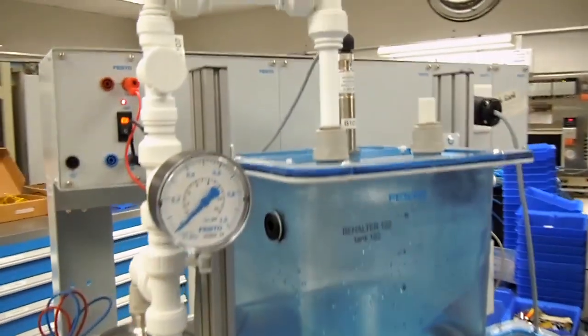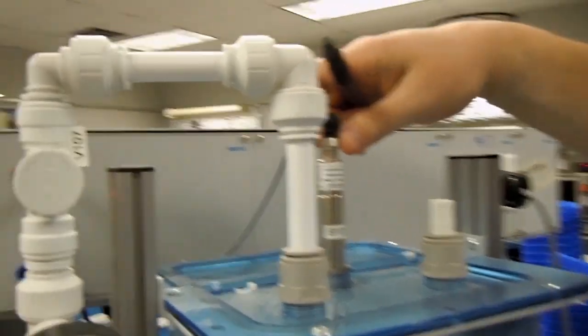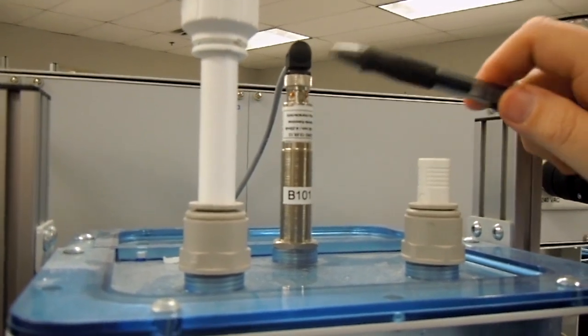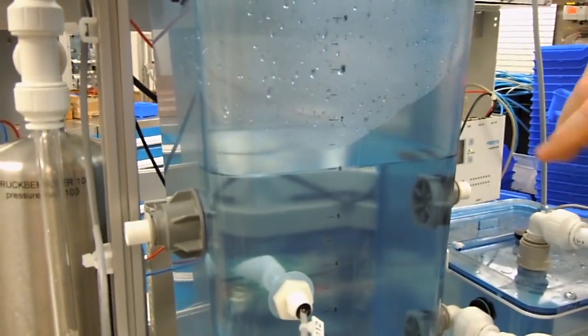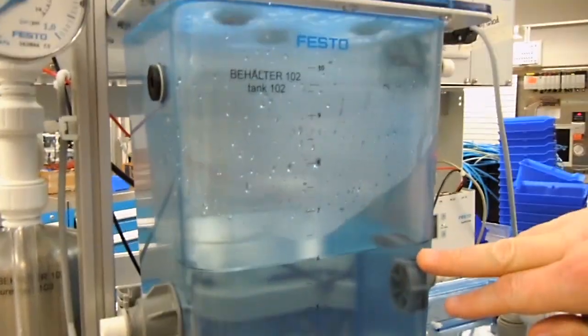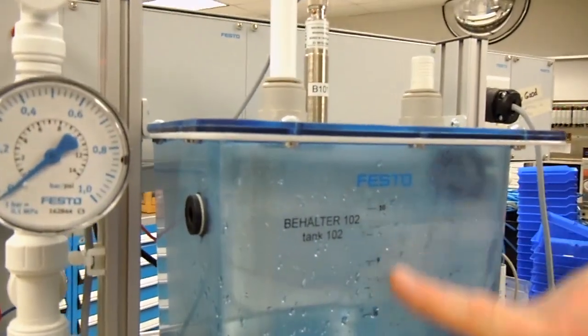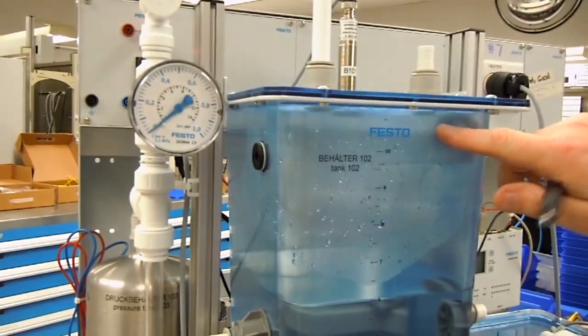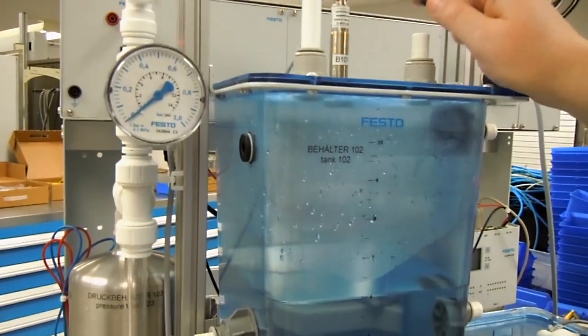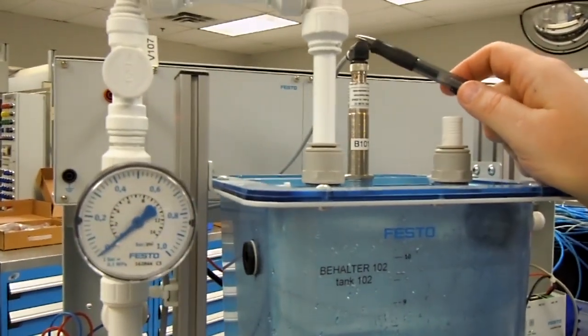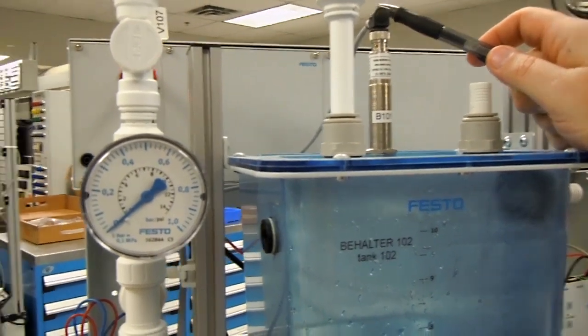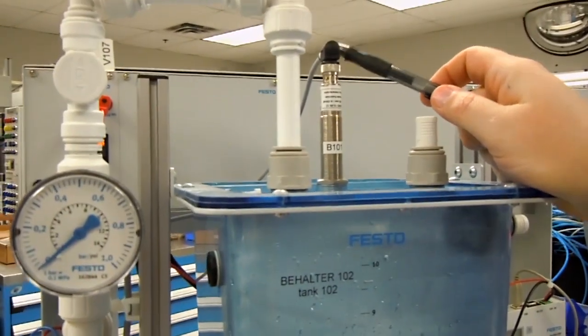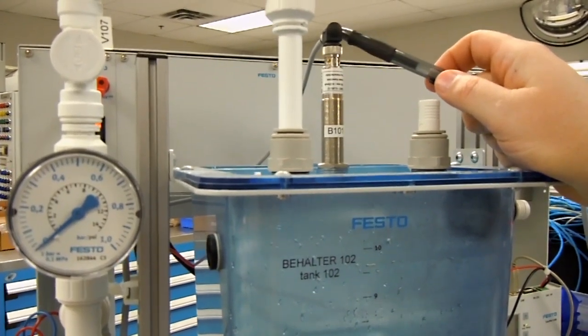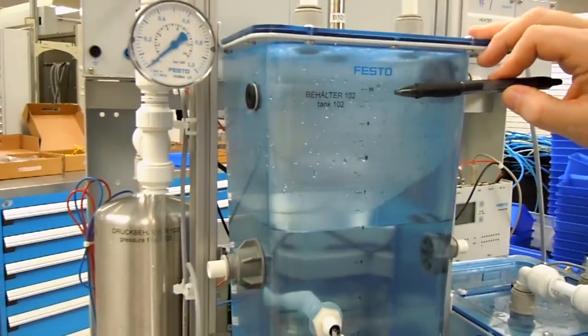Over to the, that was the third. Over to the fourth one right here. This is the ultrasound level sensor. It has a range of 0 to 300 millimeters in that tank, so it's able to tell the level by detecting the surface. It uses ultrasound, so a beam hits the surface of the water, reflects back to the sensor, and is able to measure that. Now the output of this level sensor is 4 to 20 milliamps. So it requires a converter, which there is one in the back, which we'll look at in just a second. But the output of this is 4 to 20 milliamps for a range of 0 to 300 millimeters.